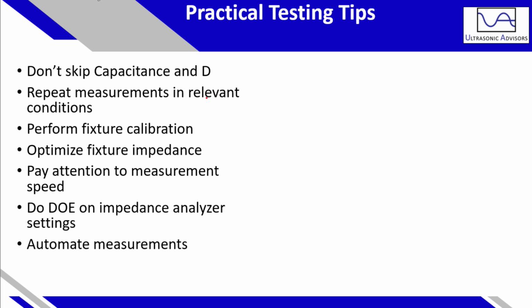So let's dive now right into the practical testing tips. The first one is don't skip measuring your capacitance and dielectric loss. Whether you're doing that with the LCR meter, if your dielectric loss is low, in the range of 0.2%, or with your impedance analyzer, utilizing the phase to calculate dielectric loss, don't skip this step. It's important. It provides another data point for analysis, and it is relevant as we discussed in session 1.